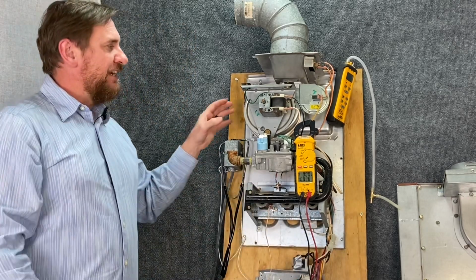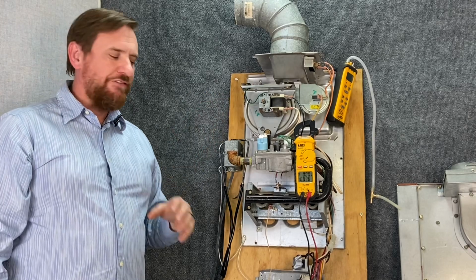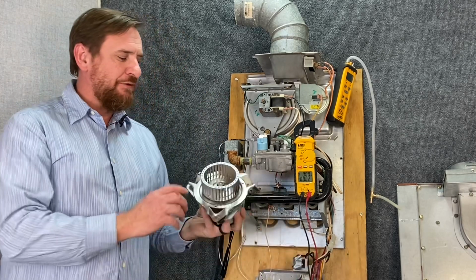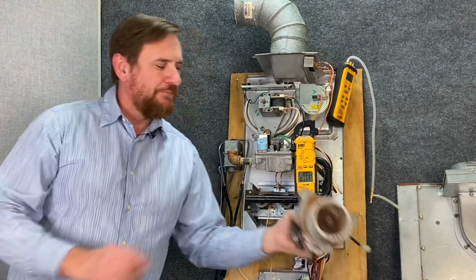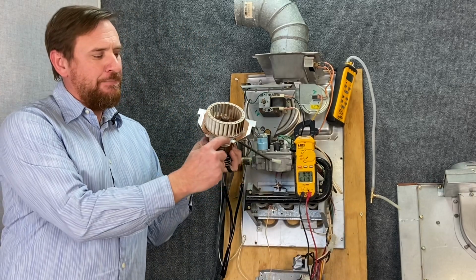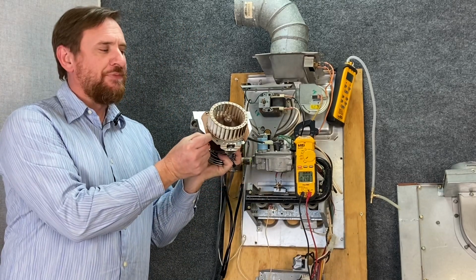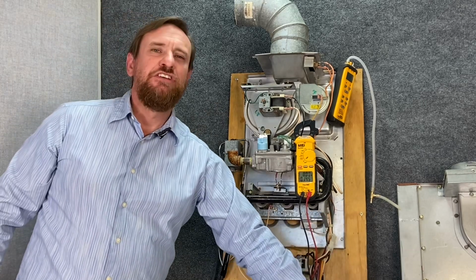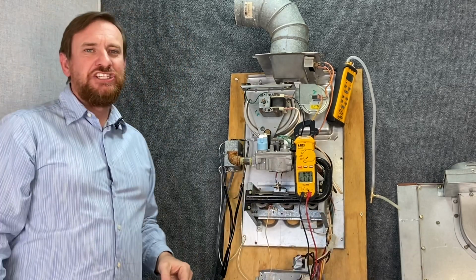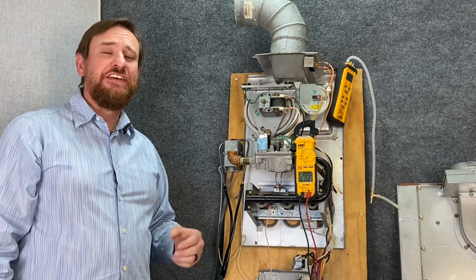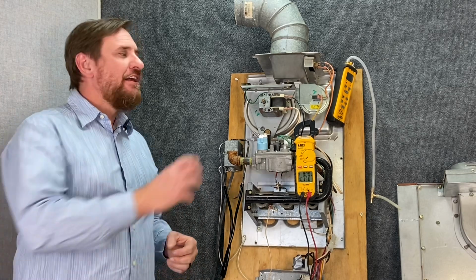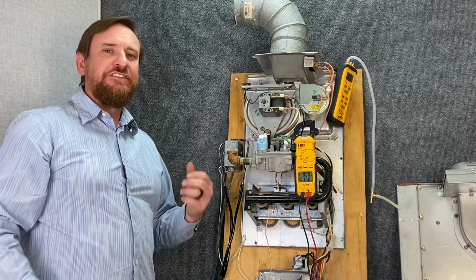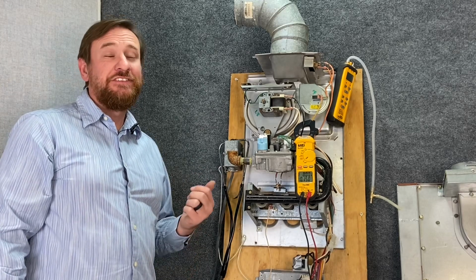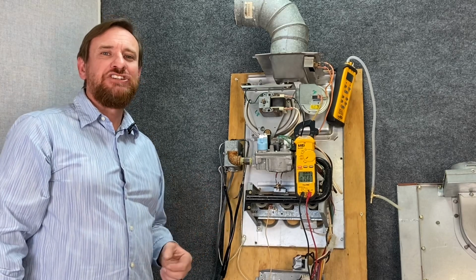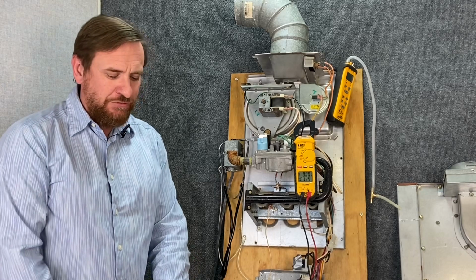But another thing we have to take into account is when we pull this motor off, we got to make sure that we are very careful with the gasket. This motor has a rubber gasket, but at the very bottom it's been ripped, it's been torn. Most of the modern gaskets use a type of fiberglass insulation as a gasket. The insulation of that fiberglass handles the high heat. So if we were to pull this motor off, there's a very high chance that we've actually damaged that gasket material. So we want to be careful with that.